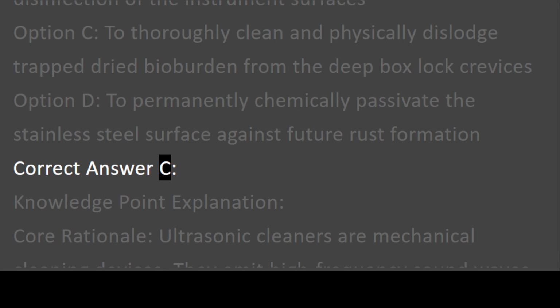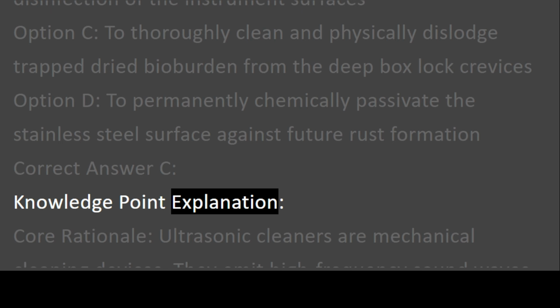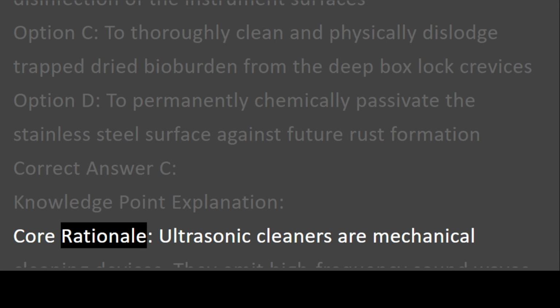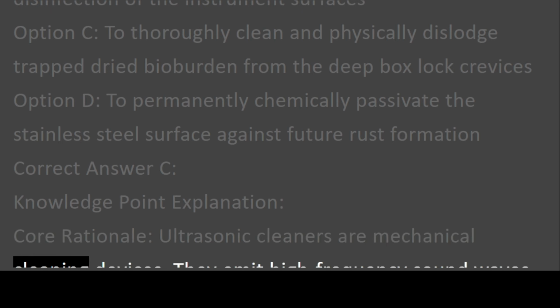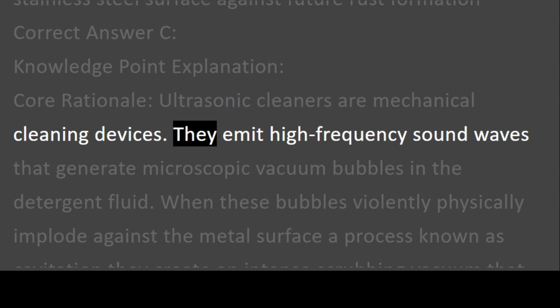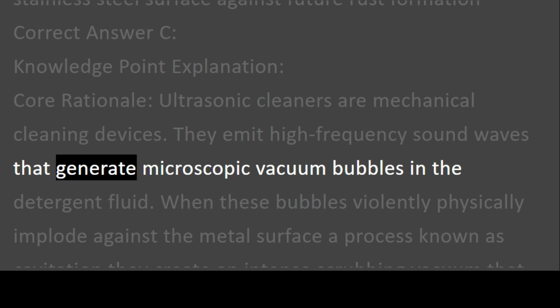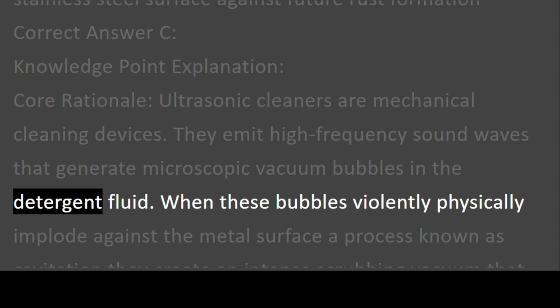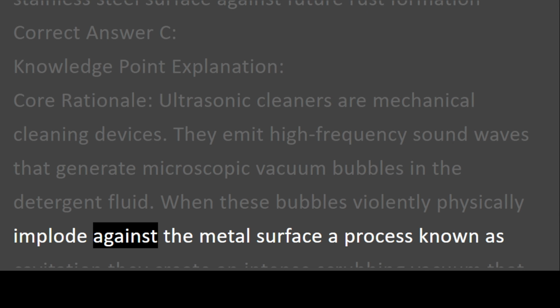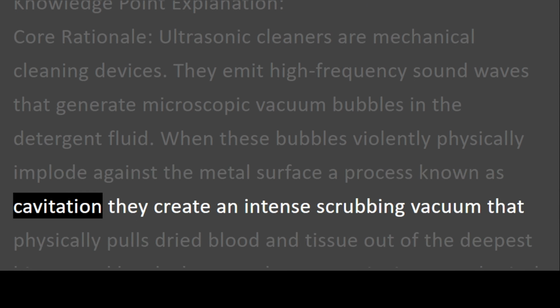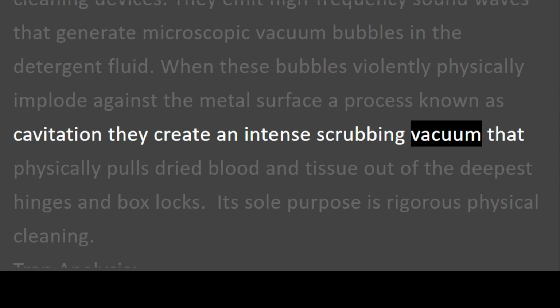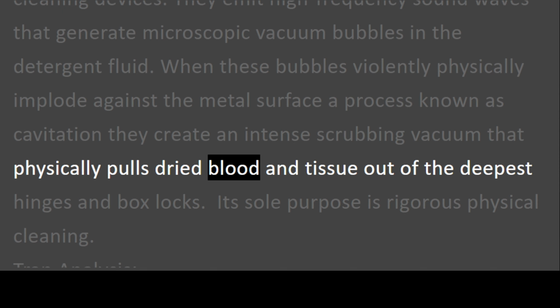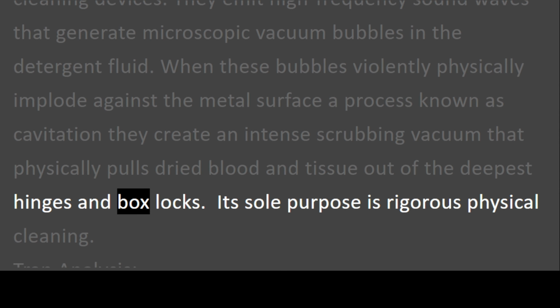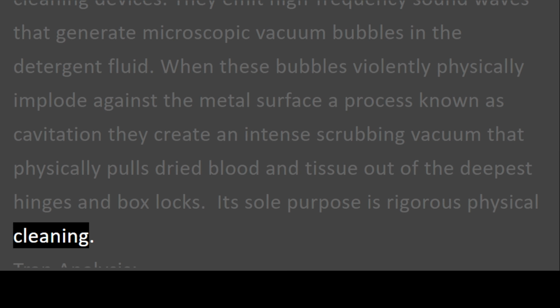Correct answer C. Knowledge point explanation. Core rationale. Ultrasonic cleaners are mechanical cleaning devices. They emit high-frequency sound waves that generate microscopic vacuum bubbles in the detergent fluid. When these bubbles violently physically implode against the metal surface, a process known as cavitation, they create an intense scrubbing vacuum that physically pulls dried blood and tissue out of the deepest hinges and box locks. Its sole purpose is rigorous physical cleaning.